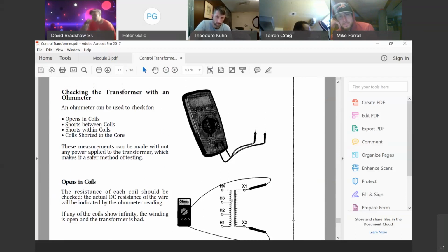Now we try to test for resistance. We're not testing for continuity, we're not listening for sound, we're not looking for voltage, so you don't need to use your volt setting. All you're trying to do is read the resistance of the secondary. You do the same thing for the resistance of the primary. You're not looking for a sound, you're trying to read the resistance of it.